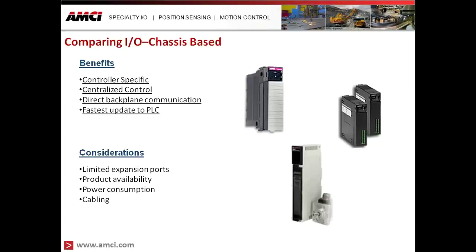Some considerations with chassis-based IO: limited expansion slots — if you buy a seven-slot rack, you can only add seven IO modules. Product availability is another factor, as some specialty IO solutions may not be available for that particular PLC. Power consumption is also a concern — some plug-in cards are quite power-hungry, and when the power supply provides power for all plug-in cards, you need to ensure you're not drawing more than the supply can provide, which can cause communication issues with the backplane.